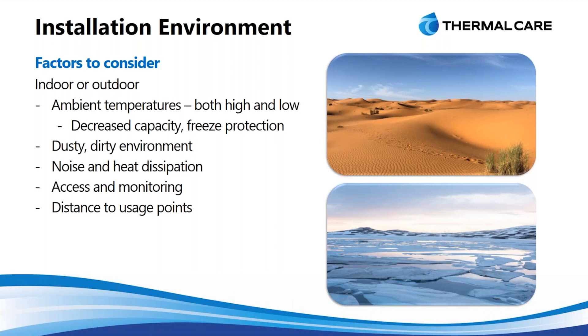On the low side, that's where we talk about the glycol mixture to protect the fluid. Because even if I am operating at a 50-degree set point, which technically would not require any glycol, I'm still sending that water outside.